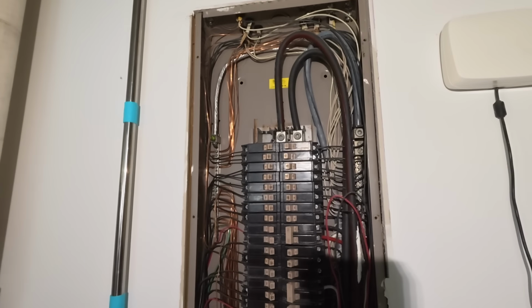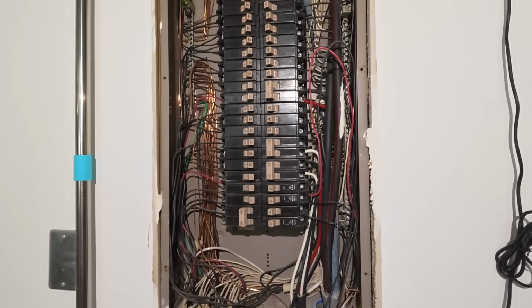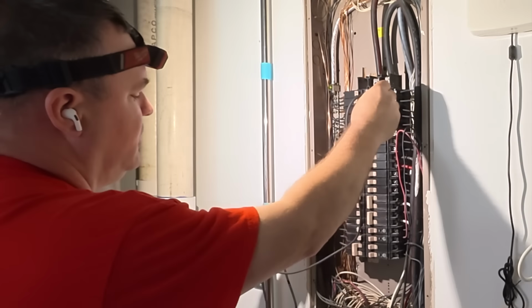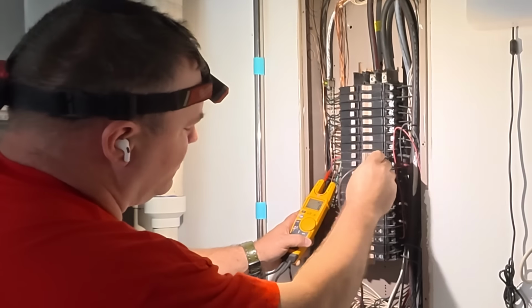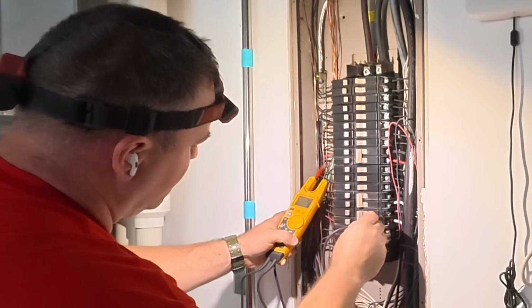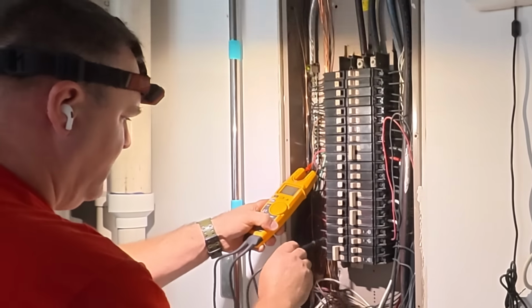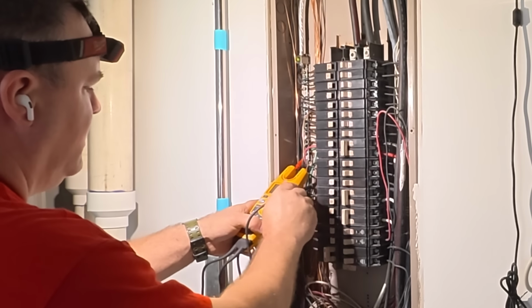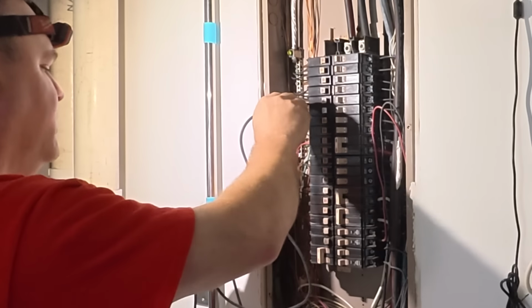It's somewhere else in one of the devices on the second or third floor. By checking each individual circuit breaker, I'm able to rule out three things: a short circuit, a ground fault, and an overload. If each circuit breaker has power, then the problem is not here, it's elsewhere in the circuit.